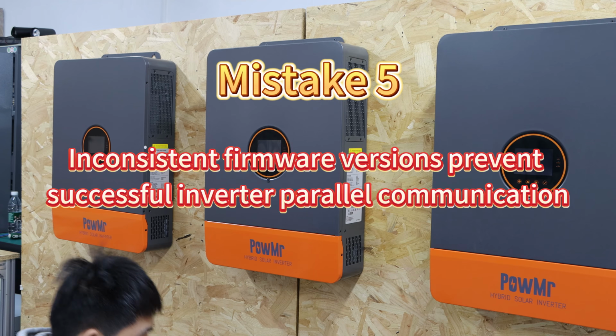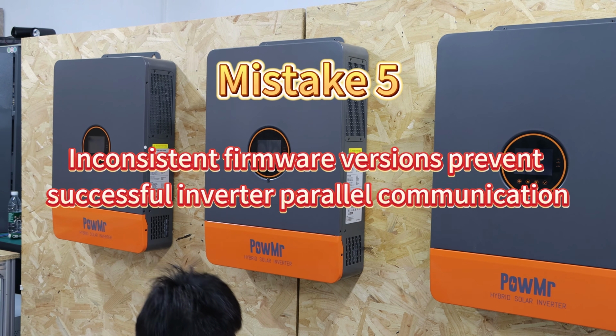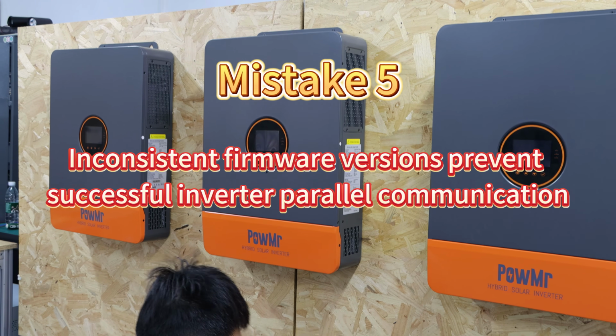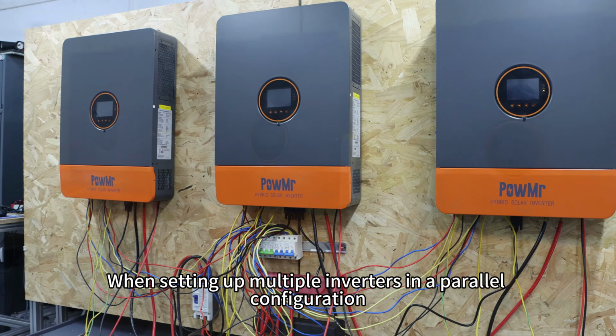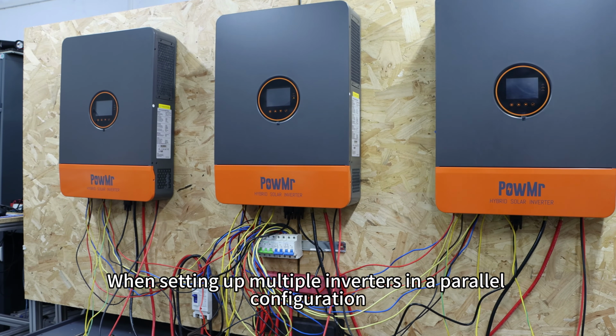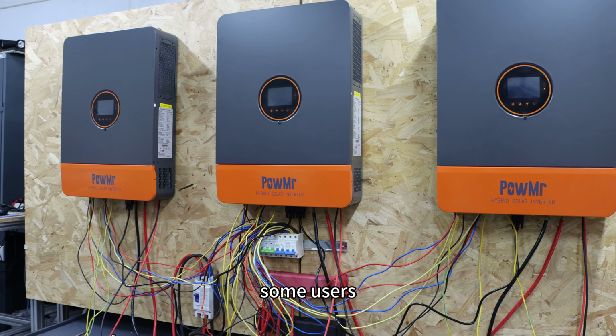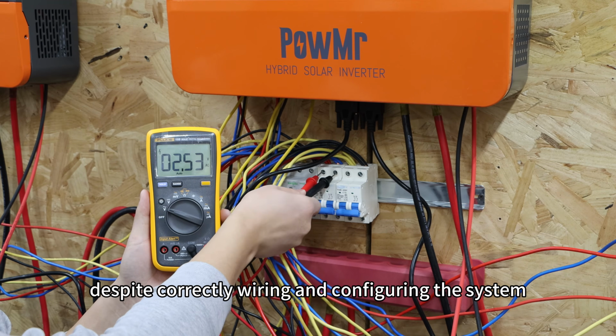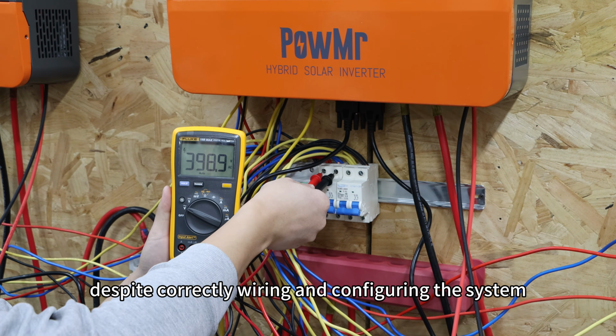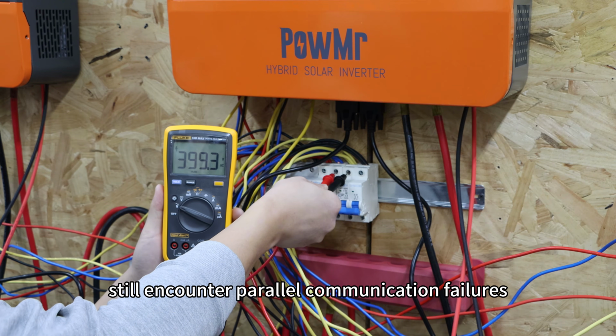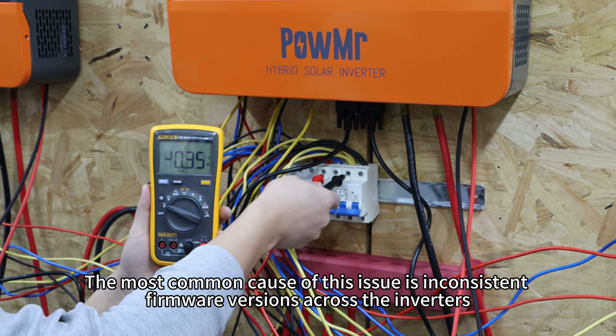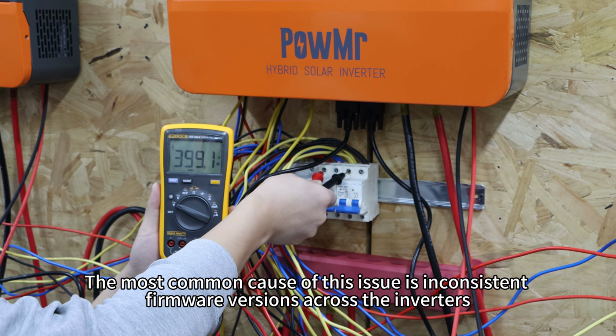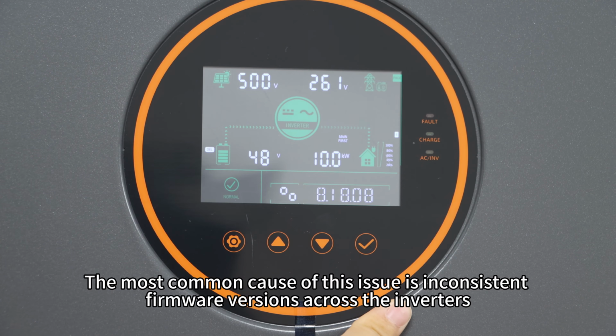Mistake 5. Inconsistent firmware versions prevent successful inverter parallel communication. When setting up multiple inverters in a parallel configuration, some users, despite correctly wiring and configuring the system, still encounter parallel communication failures. The most common cause of this issue is inconsistent firmware versions across the inverters.